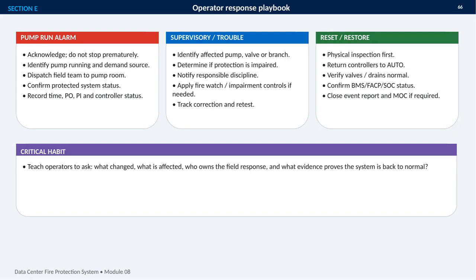This slide is an operator response playbook for 3 common conditions: a pump run alarm, a supervisory or trouble signal, and system reset or restoration. For a pump run alarm, the priority is to acknowledge the alarm without stopping the pump prematurely. I need to identify which pump is running and why, dispatch a field team to the pump room, confirm the protected system remains properly supported, and record the time, PO, PI, and controller status.